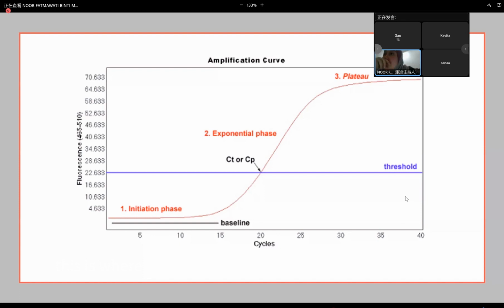number figure. Okay? Because you have your amplification along the way. And then you probably will think, so how do I choose, is it this point or this point or which point? So the machine usually, if you click automatic, will do an automatic configuration, and it will set automatically where the best fit threshold should be.